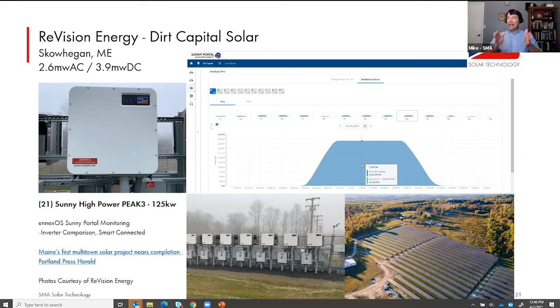The Core 1 line is 277/480, 3-phase Y only, so if you're using that there would be a transformer. For a smaller system, potentially having Sunny Boys connect line to line on the 208 grid would be a good application—I know Tyson has a lot of customers who've gone that way. So it's probably size dependent whether we'd direct you to the Core 1 with a transformer or to Sunny Boys.